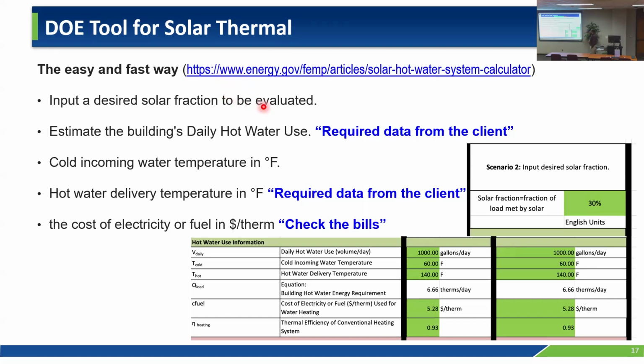First, input a desired solar fraction to be evaluated. Ask the facility manager or personnel how much energy is used, then run different simulations by changing this number — 30%, 50%, 100%. If you want to deliver all of the heat requirement from solar thermal, that's 100%; 50% of the heat requirement from solar thermal would be 50%, and so on.